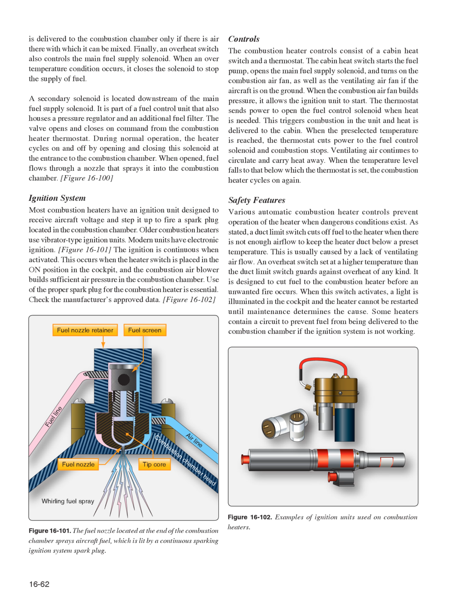A secondary solenoid is located downstream of the main fuel supply solenoid. It is part of a fuel control unit that also houses a pressure regulator and an additional fuel filter. The valve opens and closes on command from the combustion heater thermostat. During normal operation, the heater cycles on and off by opening and closing this solenoid at the entrance to the combustion chamber. When opened, fuel flows through a nozzle that sprays it into the combustion chamber.